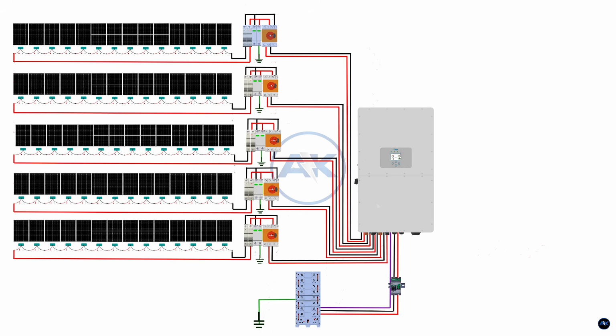Do not turn on the battery before the communication cable is connected. Without communication, the inverter cannot properly control charging and discharging. Once grounding, power cables, and communication are complete, double-check everything. Confirm correct polarity, tight connections, proper cable routing, and secure grounding. Only after all checks are complete should you turn on the battery breaker. The battery will power up and the inverter will detect the battery through the BMS. This completes the battery to inverter electrical connection.